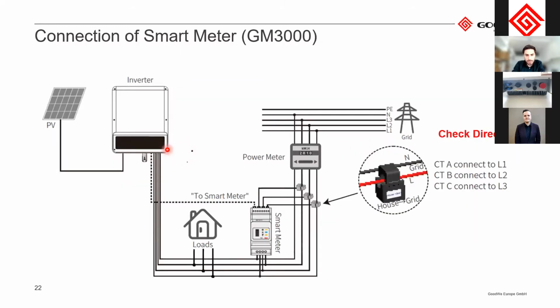So here you see how to connect the smart meter. So for a 3-phase inverter, you need a GM3000. And basically you connect here on the top side, you have the connection pins for the CTs. And then you have the connection pins for the inverter. And on the lower side, you just have the voltage sense.